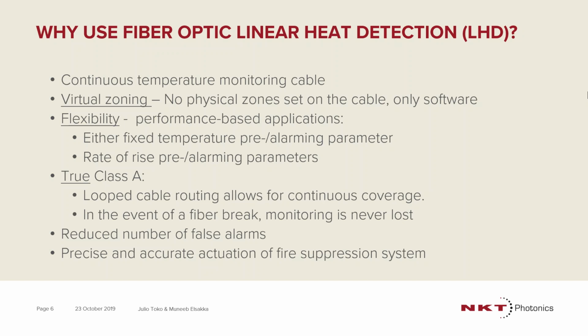Thank you, Louis. So continuing on to why use fiber optic linear heat detection as opposed to the conventional LHD systems. This allows you to have continuous temperature monitoring along the full length of the cable. There is no physical zoning that has to be set up on the cable. Rather, you have more of a virtual zoning that can be done through software.